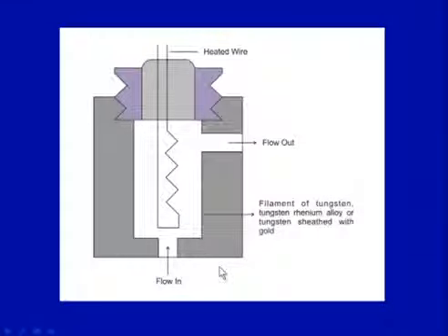One limitation could be that it has low sensitivity. Now, this is a very simple schematic of this thermal conductivity detector. As you can see, there is a filament here.